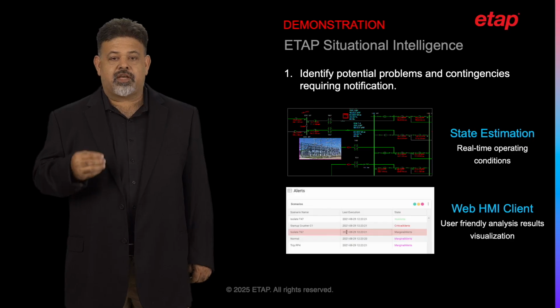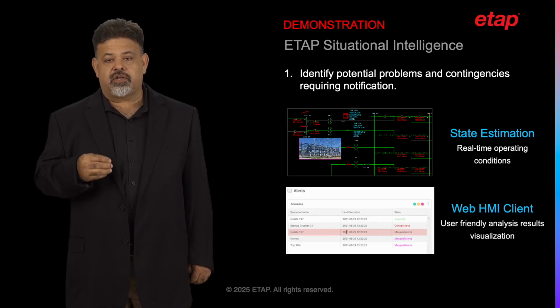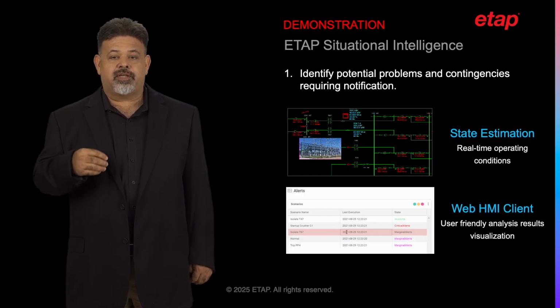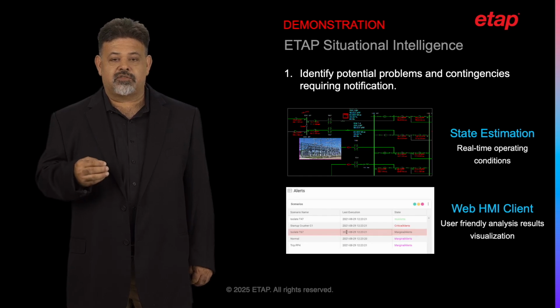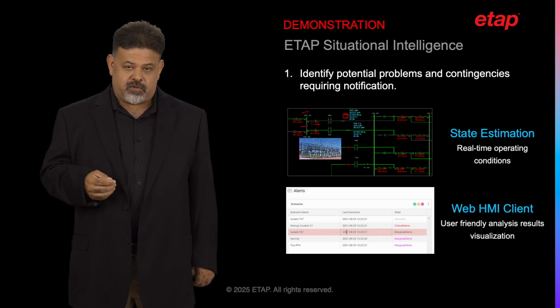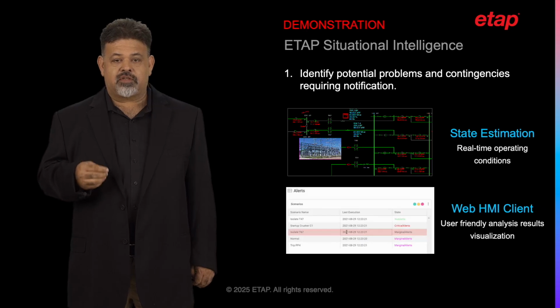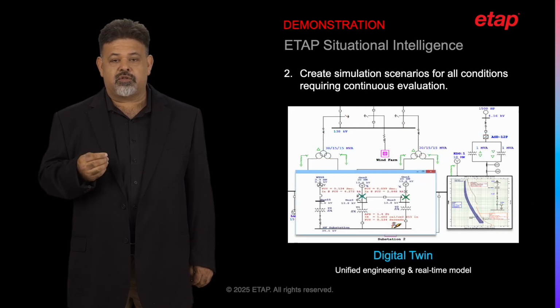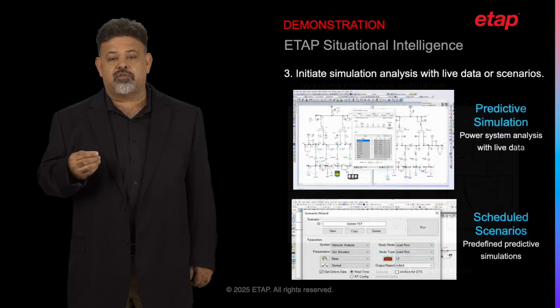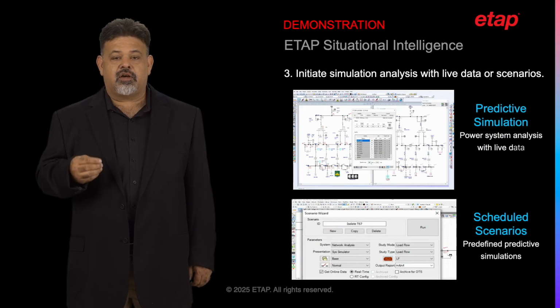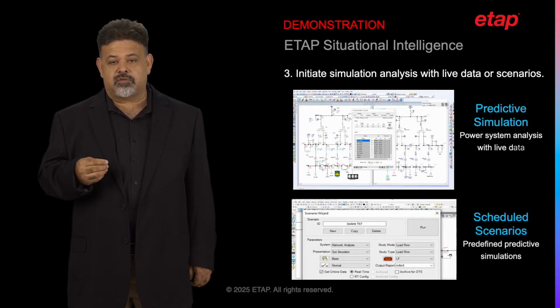This feature is a critical app for control room operators for secure and efficient power system operation, by identifying potential unsafe actions and conditions. First, users identify potential problems and contingencies that require the operators to be notified in case a potential unsafe condition is detected. Leveraging the intelligence of the ETAP predictive analysis tools, engineers can first identify and create simulation scenarios for all conditions that will require to be continuously evaluated, as they may cause a significant impact to the operation.